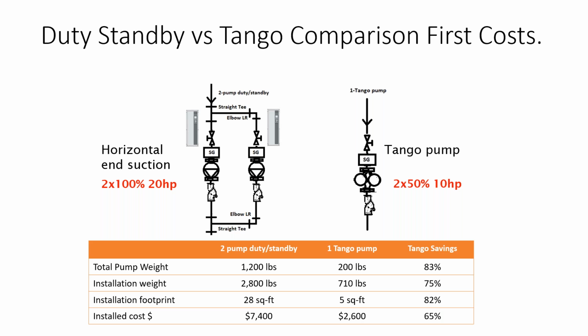I know in most of our applications, even in the retrofit applications, where we may have had 2 pumps, we don't have the room anymore because the cooling towers get bigger and the other controls have taken up square footage in the space. So we really need a solution that will take up 82% less than what's currently in there. And once again, the cost of installation, 2 pumps versus the 1 pump Tango solution, is substantially less, at 2,600 versus 7,400.